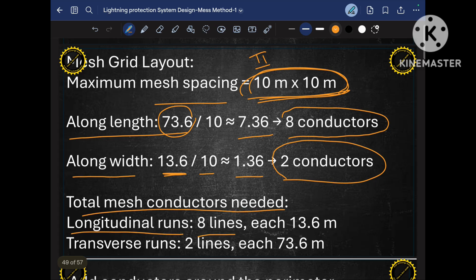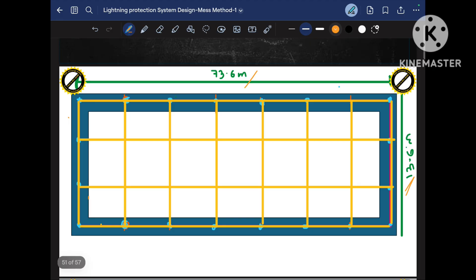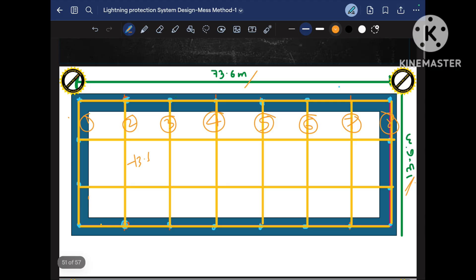So the total MESH conductors needed are: longitudinal run — 8 lines, each 13.6 meters; and transverse run — 2 lines, each 73.6 meters. Our project has length 73.6 meters and width 13.6 meters. The 8 longitudinal runs go across the width, so each is 13.6 meters long. The 2 transverse runs go along the length of the building, so each is 73.6 meters long. So we have calculated the MESH conductor layout.